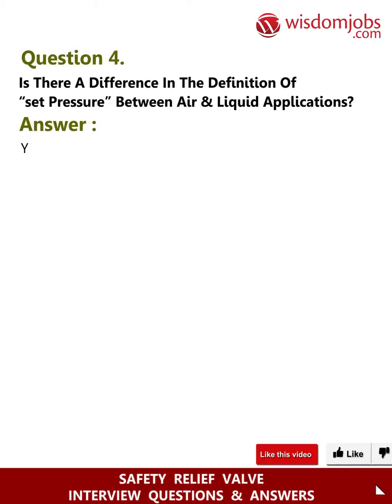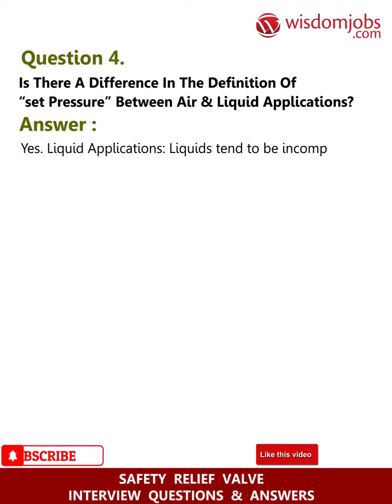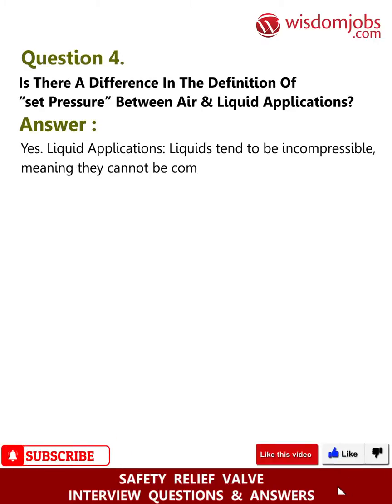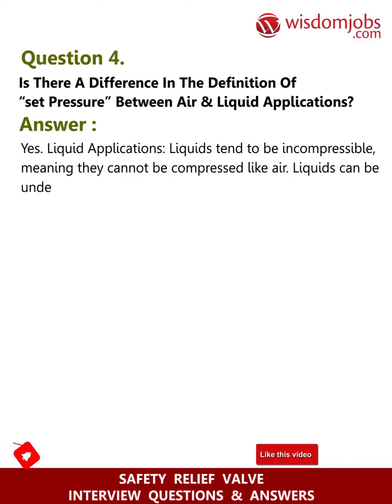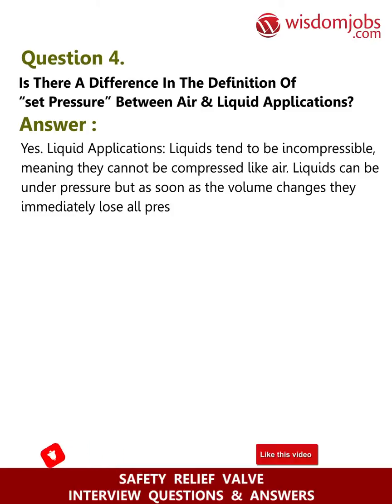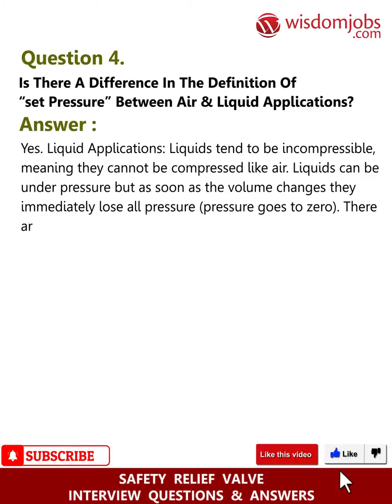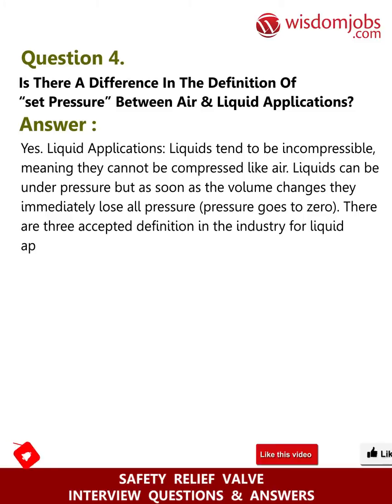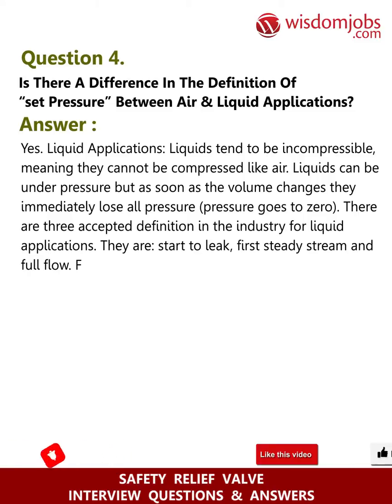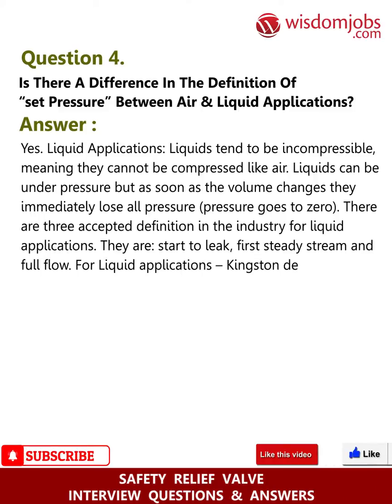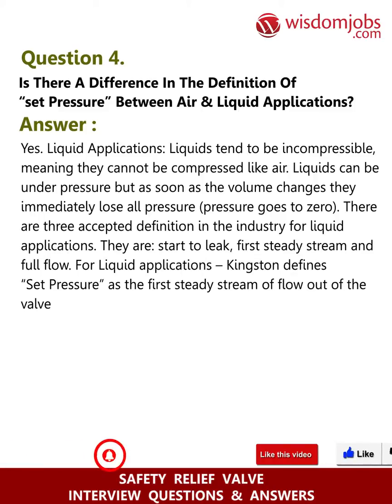Question 4: Is there a difference in the definition of set pressure between air and liquid applications? Answer: Yes. Liquids tend to be incompressible, meaning they cannot be compressed like air. Liquids can be under pressure, but as soon as the volume changes they immediately lose all pressure — pressure goes to zero. There are three accepted definitions in the industry for liquid applications: start to leak, first steady stream, and full flow. For liquid applications, Kingston defines set pressure as the first steady stream of flow out of the valve.